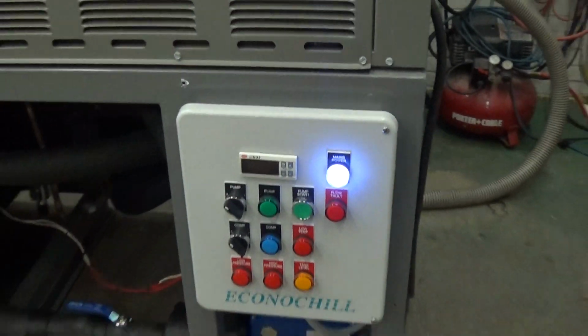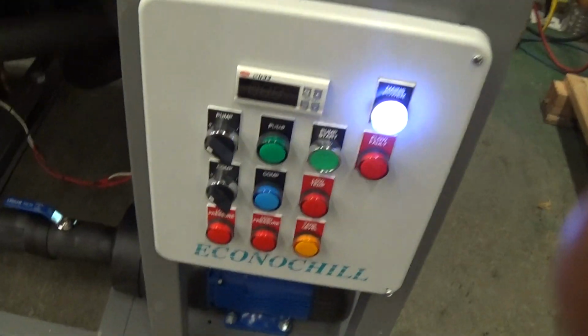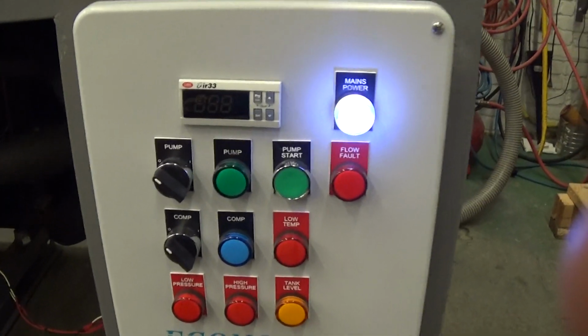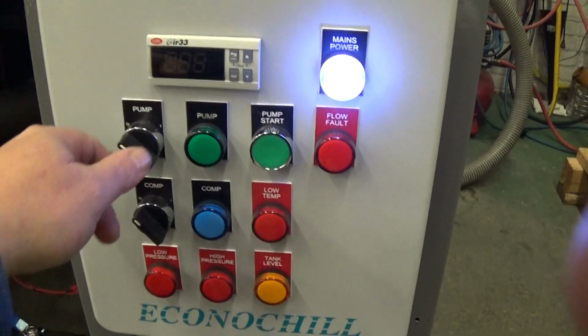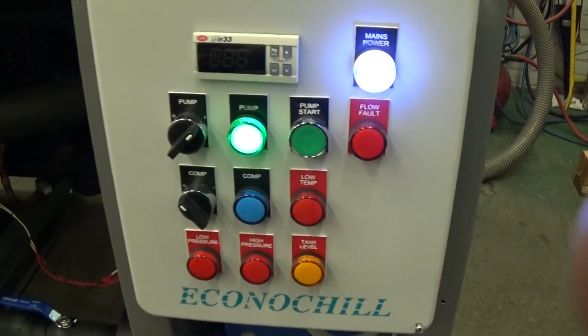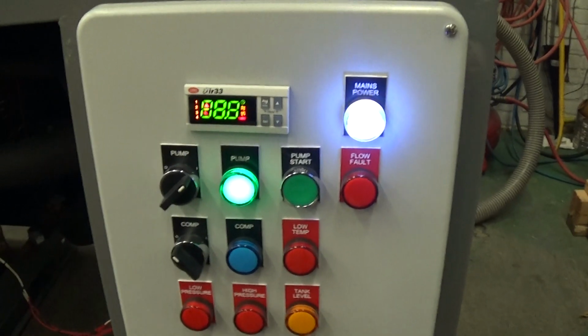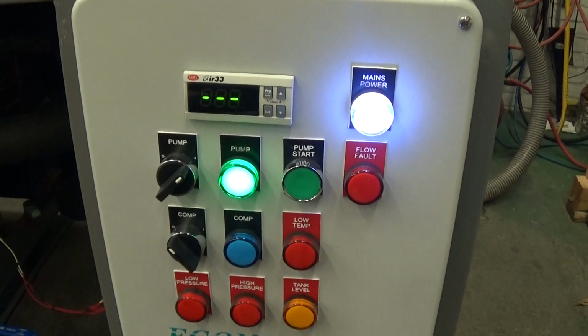If you're going to turn your chiller on and off regularly during the week, do it from the control panel here. Do not do it from your main power disconnect. So again, here's our controller. First thing we're going to do is just turn the pump on. And the controller will just kind of boot up here.